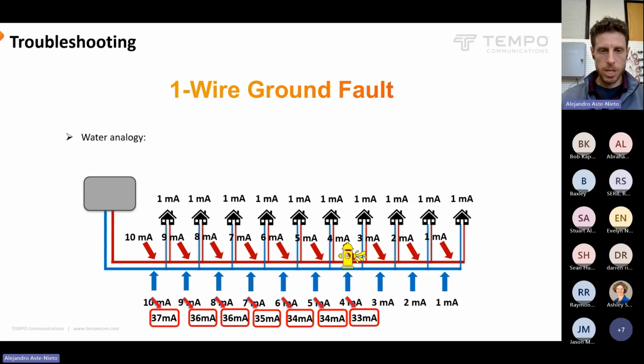So again, with our analogy here, think of it in terms of a fire hydrant that somebody hit and it's spewing water out into the nearby grass. It's not getting to the sewer line, but you're still seeing a ton of water flowing through the water main. So you're going to see high amounts of usage here up until the fire hydrant, but that clue is not there on the red side.